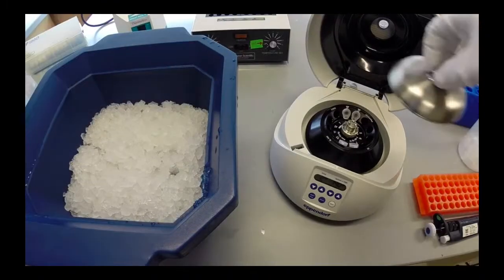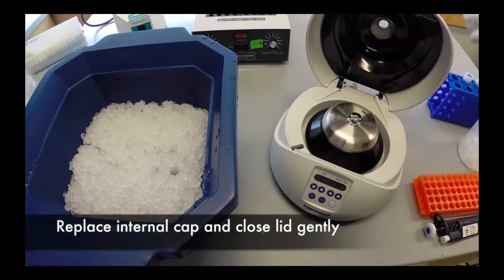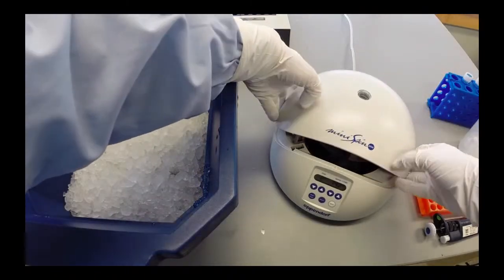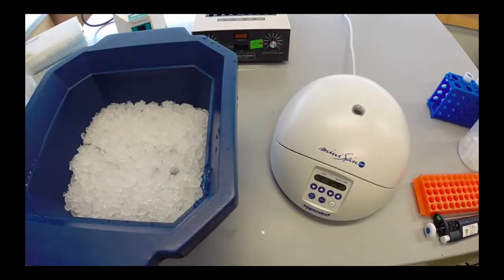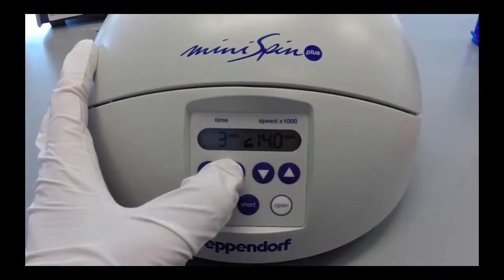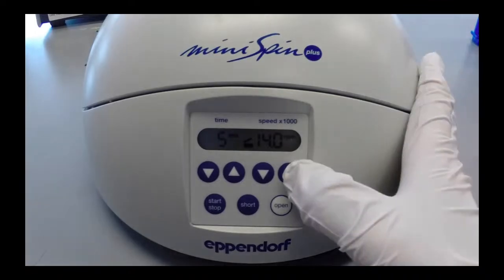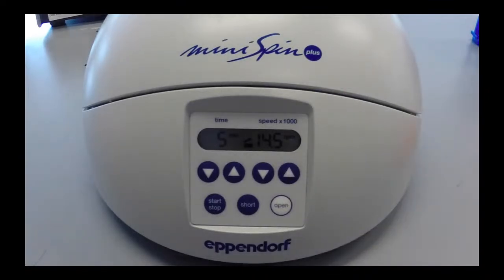Replace the metal lid and press it until it clicks securely onto the rotor. Close the lid to the microcentrifuge gently. Change the centrifugation time by pressing the arrows to the desired time, in this case, 5 minutes. Press the arrows by the speed to navigate to the proper RPM. In this case, 14.5 thousand RPM is the max this centrifuge can perform and is close enough to our desired speed. Press the start button.